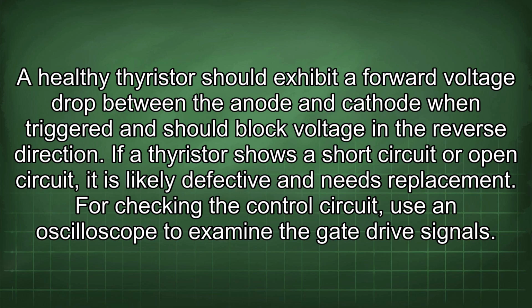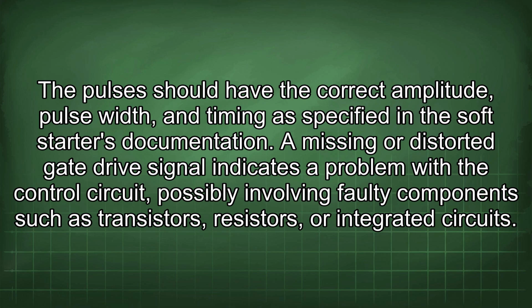For checking the control circuit, use an oscilloscope to examine the gate drive signals. The pulses should have the correct amplitude, pulse width, and timing as specified in the soft starter's documentation. A missing or distorted gate drive signal indicates a problem with the control circuit, possibly involving faulty components such as transistors, resistors, or integrated circuits.